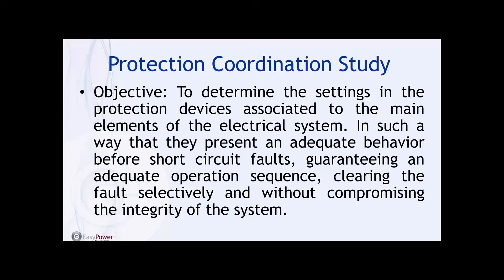Let's move forward to the relay coordination study. I apologize because an hour isn't enough, but we were able to show you the different functions EasyPower has. So let's talk about the protection coordination study, or relay coordination study. This is basically the same objective you usually have in other projects: to get all the settings for the relays in order to have adequate behavior for short circuit faults, a proper operation sequence, clearing the fault, and selectivity without compromising the integrity of the system. The objective is the same as you usually have in your projects, nothing special.